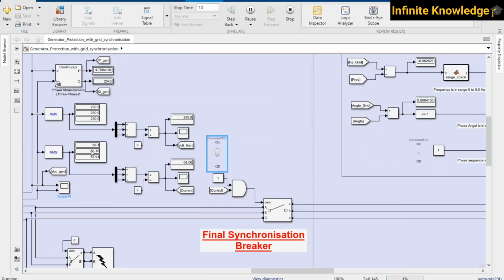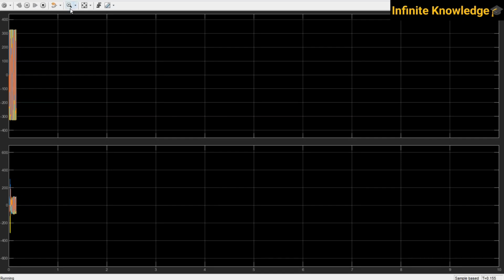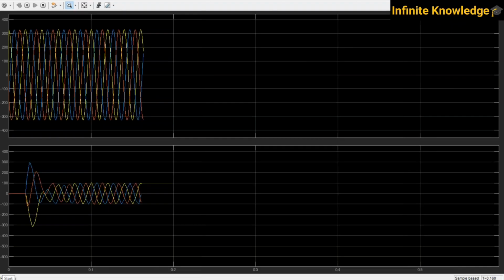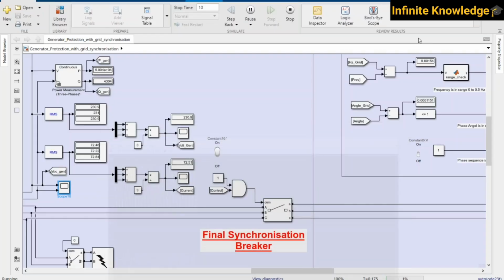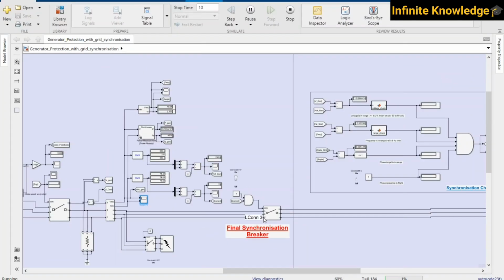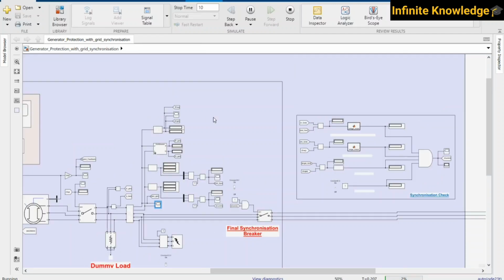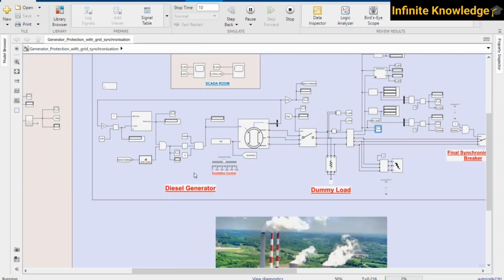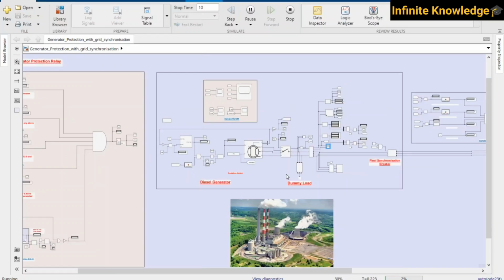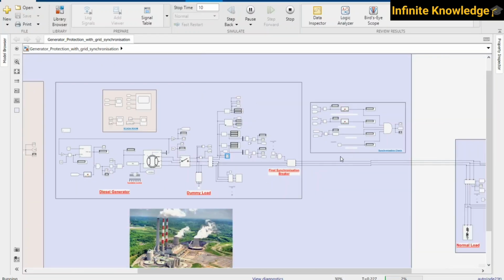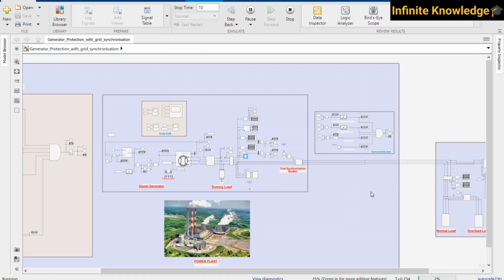So yes, initially there is slight variation. I recently synchronized the breaker, so you can see it will increase and then it takes some time to decrease. Okay, so we are just at 0.2 level, and if you want exact simulation, you need to run this simulation for 5 to 6 seconds at least, or it may take half an hour or maybe 1 hour, but you will check the exact waveform that I have earlier explained. Okay, so this is how the generator stations work, and this is how the power plants are synchronized with the grid nationally.